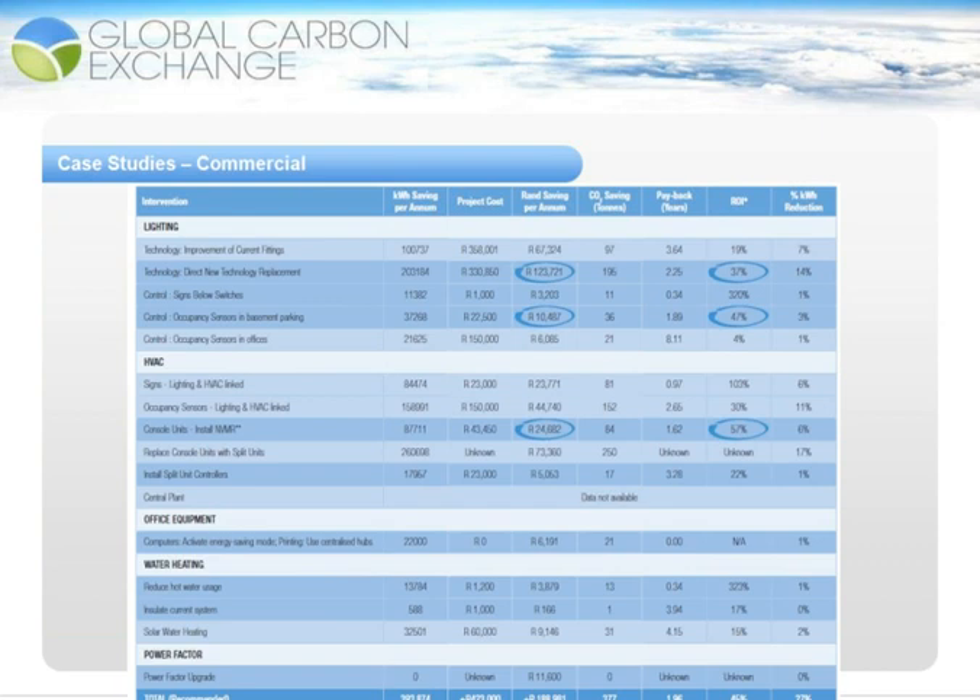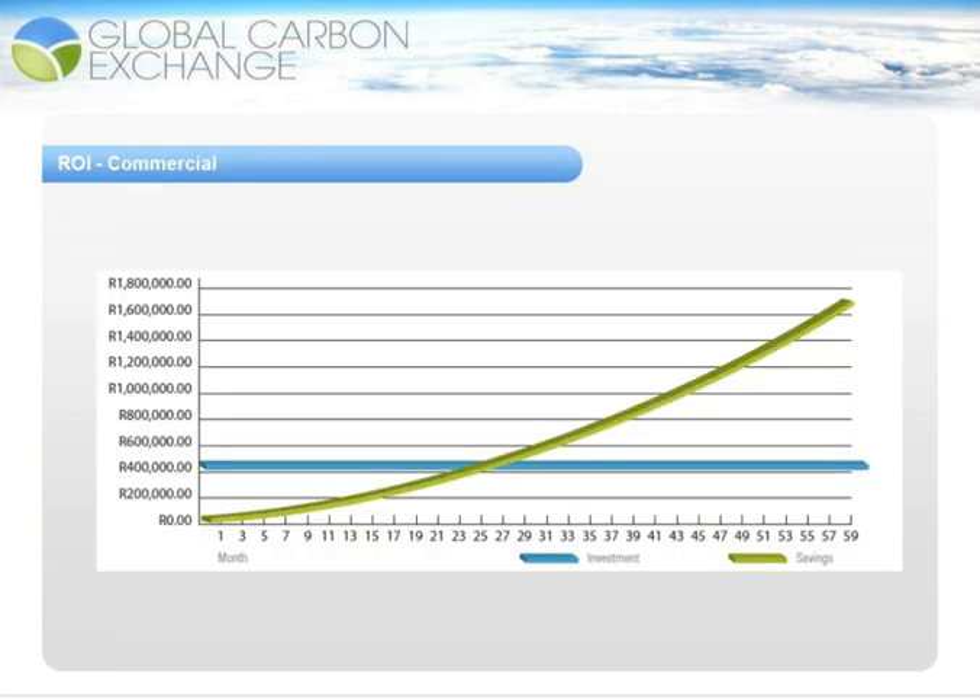The saving was 377 tonnes of CO2 per year with a payback of just under two years and an ROI of 45%. Interventions recommended included occupancy sensors for basement parking lights, direct new technology replacement for old inefficient lighting, and control measures to ensure the HVAC system only operated when required — as it was found that HVAC operated frequently at night due to individual units left on by staff. Over five years, nearly R1.8 million will be saved from an initial investment of just over R400,000, taking into account significant Eskom energy price increases.